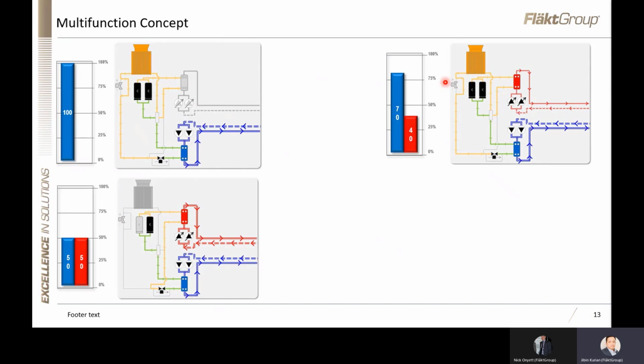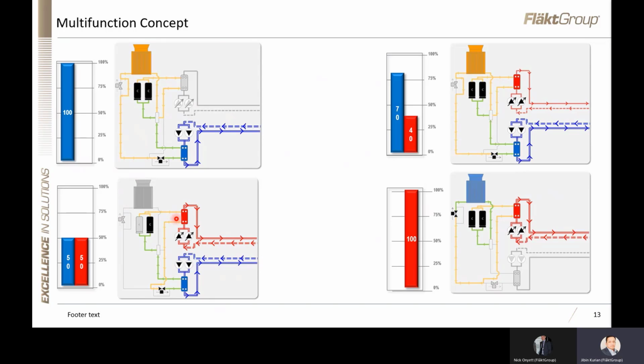And if you have 50% heating and 50% cooling demand, then the system works as full or total recovery. So whatever energy you absorb from the cooling circuit, you throw back into the heating circuit. In this mode, it works exactly as a water-cooled chiller. And if your demand is only heating, then your cooling circuit is deactivated and only your heating circuit will be operating. When you have 50-50 demand, it works as a water-cooled chiller. This is the time the heat pump is working at its best efficiency. This is a solution where you can have cooling, or heating, or simultaneous heating and cooling. So, an all-in-one solution.